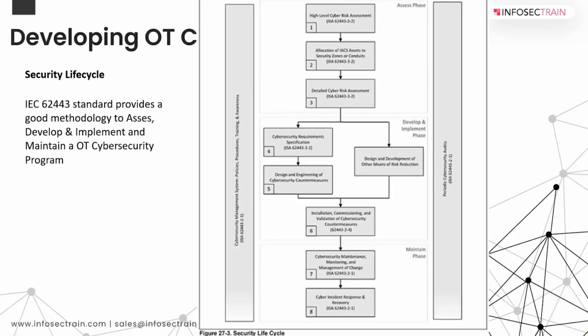So the security lifecycle I was talking about, right? The IEC 62443 standard has a very good methodology to assess, develop, implement, and maintain OT cybersecurity. How do you go about it? You start with the high level. This is the assess phase. You have this high-level cyber risk assessment. Then you identify all the assets. Once you identify all the assets, you classify them into different security zones and conduits.